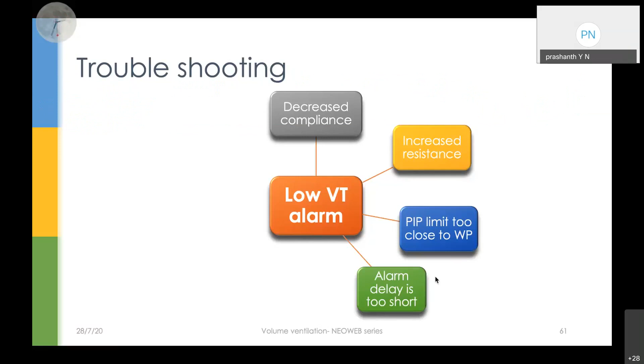And this is another important thing which you guys need to understand. The alarm delay, if we keep it too short, which is an option in Draeger, then when there is a problem the ventilator starts giving alarms as soon as there is a problem. We know that sometimes there could be a little bit of secretion, we can go in the next breath. Sometimes the circuit position could be changed, the ET position could be changed, or the baby is breathing, whatever it is. So breath to breath, it actually keeps changing.